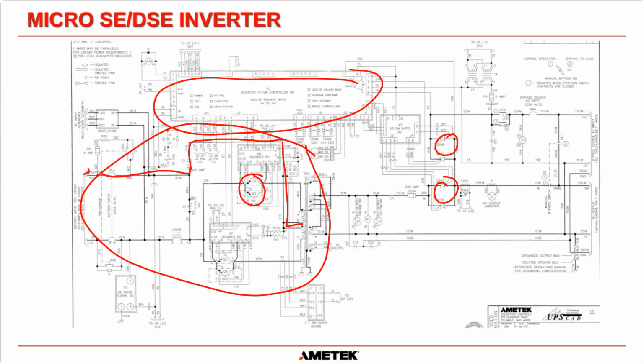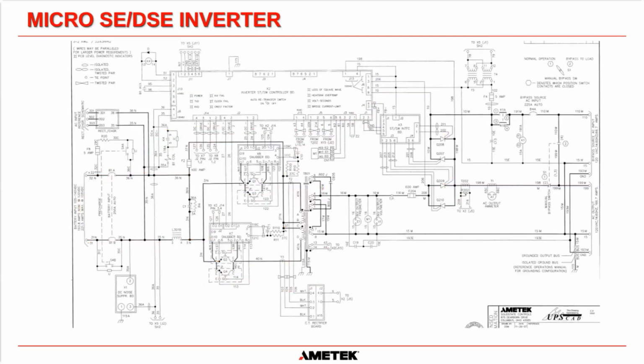If you want a higher kVA inverter bridge, we will just put more IGBTs in parallel to give you the current that's required. So you can still look at that as one switch, Q1, for example, and then this one is Q2, okay? And as you can see, we're still going down through that, back to the negative on that one, and back to the negative on that one when necessary. So it is exactly the same as that simplified drawing that I gave you.